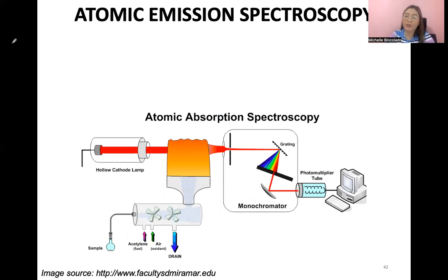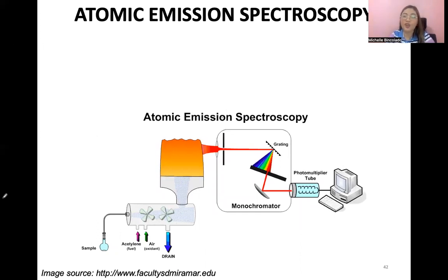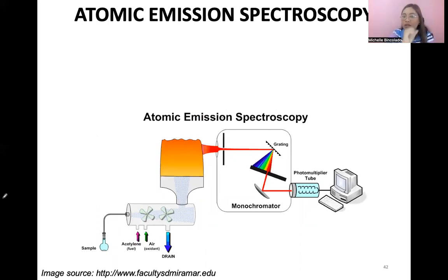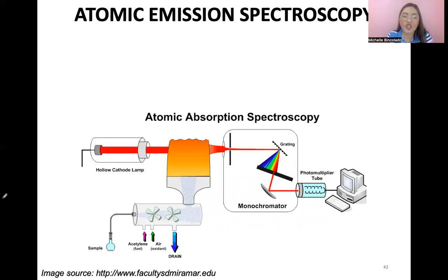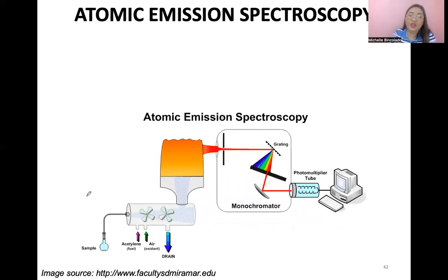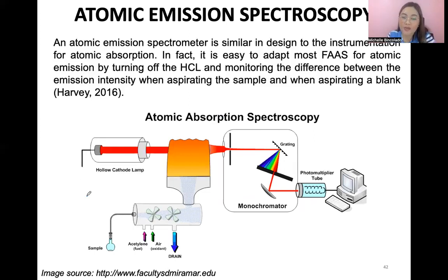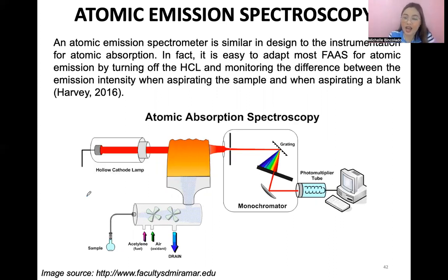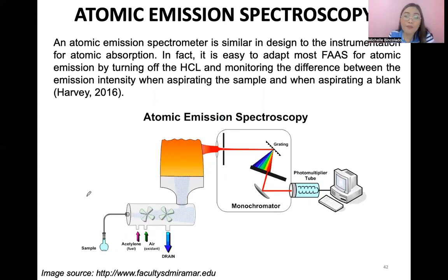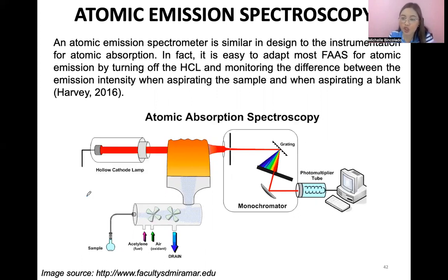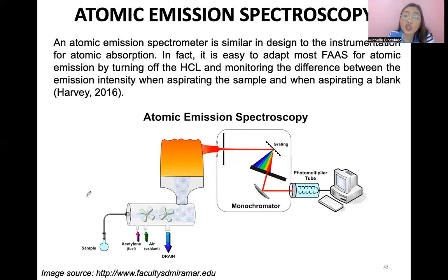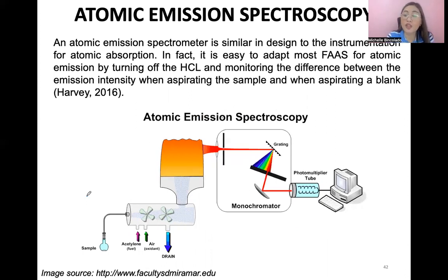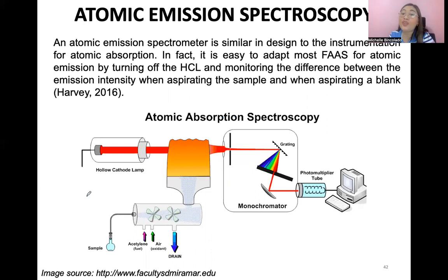So, anong difference ma'am ng AAS sa AES? O, napansin niyo itong video na to, itong animation na to, guys. Nakikita niyo ba? O, diba? So, AAS, may hollow cathode lamp. Napansin niyo, natanggal siya. You can deactivate, actually, the lamp for AAS to be converted to AES. An atomic emission spectrometer is similar in design sa instrumentation, guys, ng AAS. In fact, it is easy to adapt most flame atomic absorption spectrometers for atomic emission by just turning off the hollow cathode lamp and monitoring the difference between the emission intensity when aspirating the sample and that of the blank.